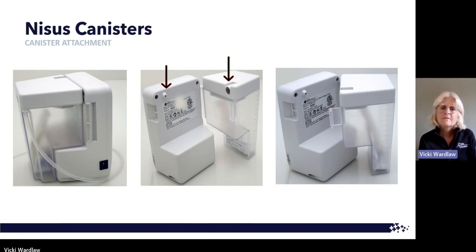Your canister has the solidifying agent in it. It also has deodorizers. The tubing is attached. There's a clamp on your tubing. So it is all self-contained, and is disposed of in your typical disposal in your care setting. And then we have also put a maze design in the top of the canister that makes it very, very difficult for any drainage to egress into the device itself. The canister goes on with a pivot hinge and a very light snap-on, and comes off very easily for our more arthritic patients. And the frequency of canister change is not any different with this. It's when the canister full alarm sounds, or once a week.